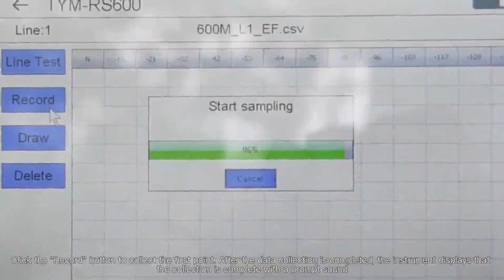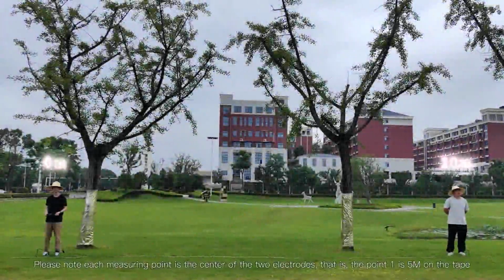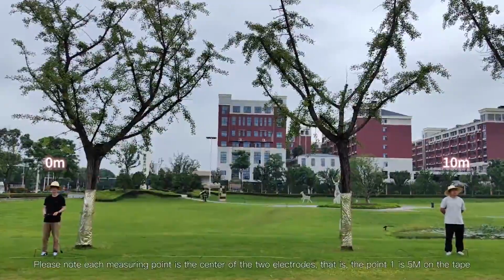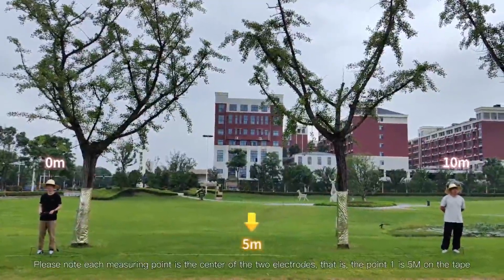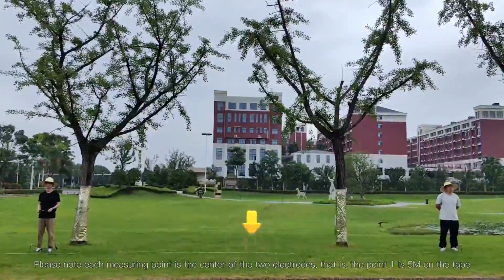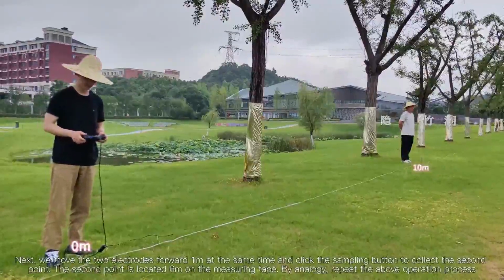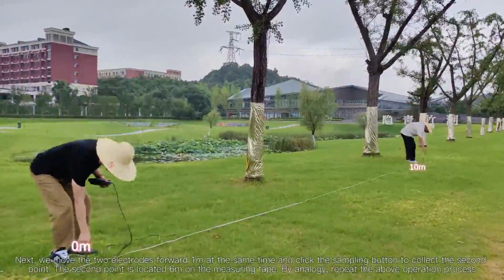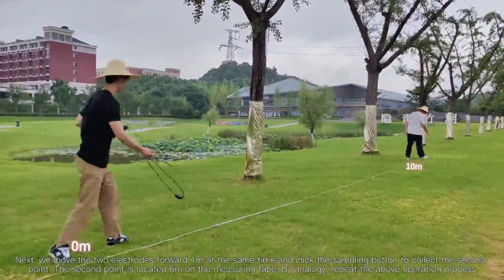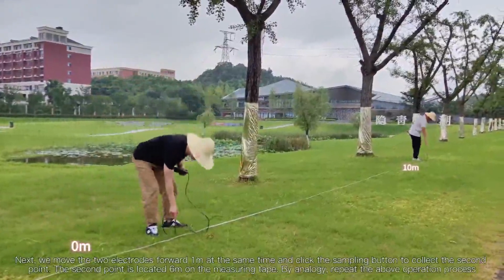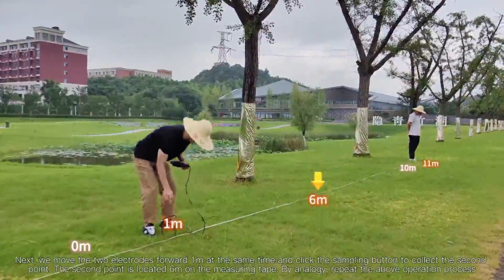After the data collection is completed, the instrument displays that the collection is complete with a prompt sound. Please note each measuring point is the center of the 2 electrodes. That is, point 1 is 5 meters on the tape. Next, move the 2 electrodes forward 1 meter at the same time and click the sampling button to collect the second point. The second point is located at 6 meters on the measuring tape.